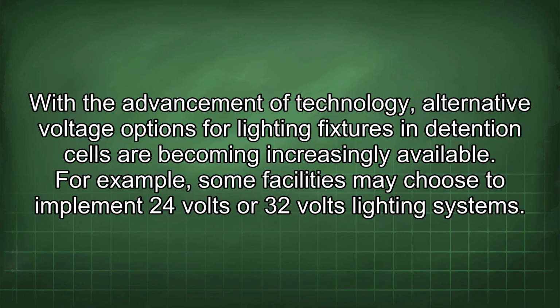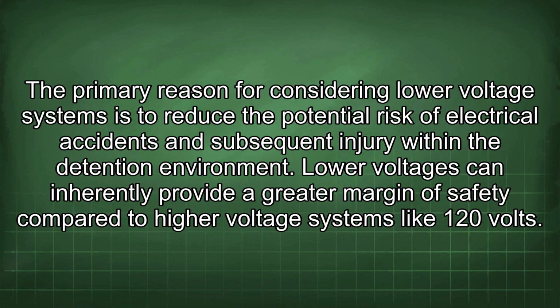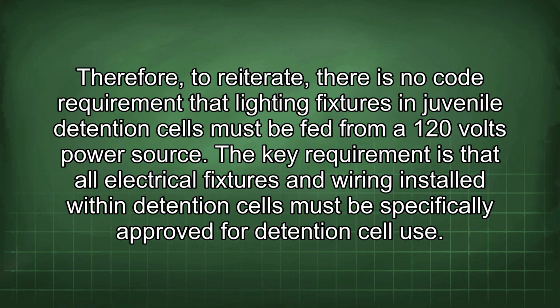With the advancement of technology, alternative voltage options for lighting fixtures in detention cells are becoming increasingly available. For example, some facilities may choose to implement 24 volts or 32 volts lighting systems. The primary reason for considering lower voltage systems is to reduce the potential risk of electrical accidents and subsequent injury within the detention environment. Low voltages can inherently provide a greater margin of safety compared to higher voltage systems like 120 volts. Therefore, to reiterate, there is no code requirement that lighting fixtures in juvenile detention cells must be fed from a 120 volts power source.